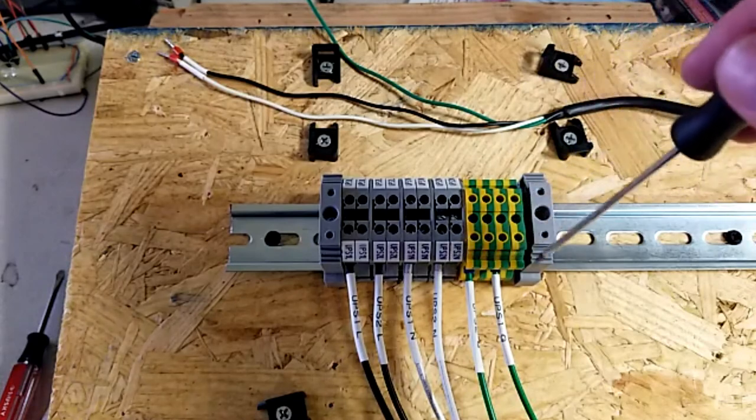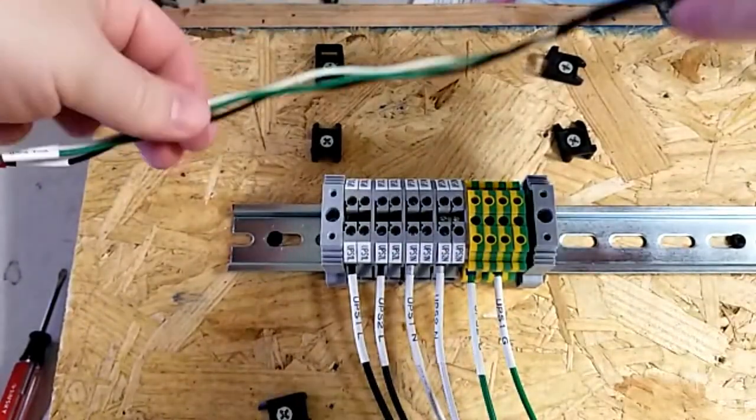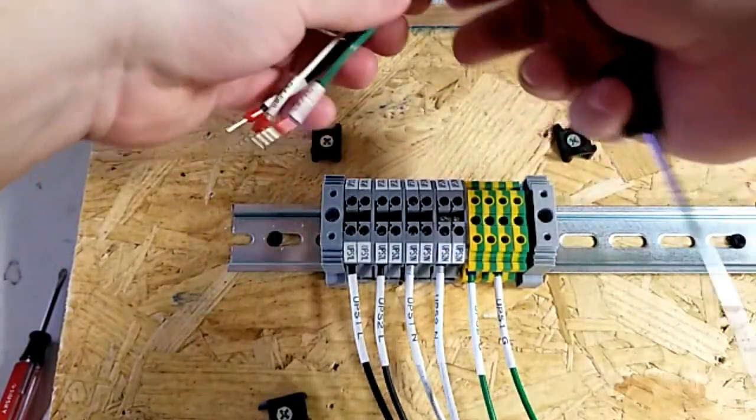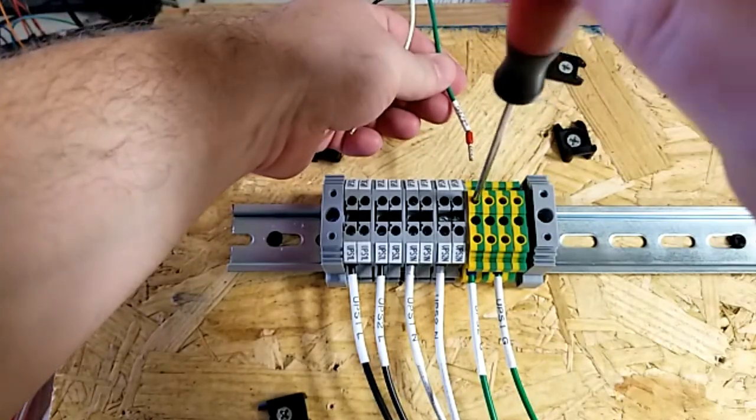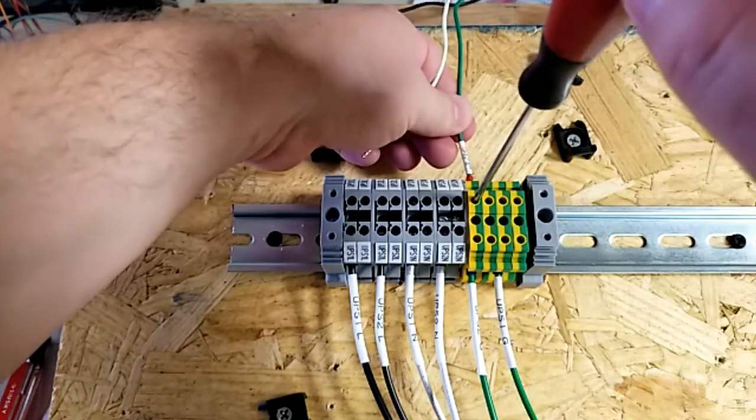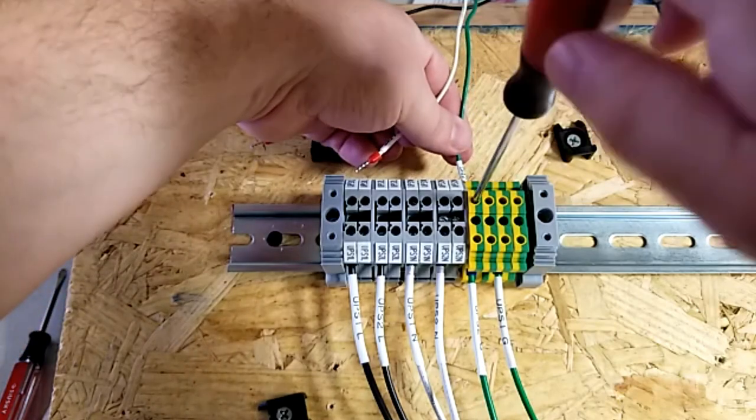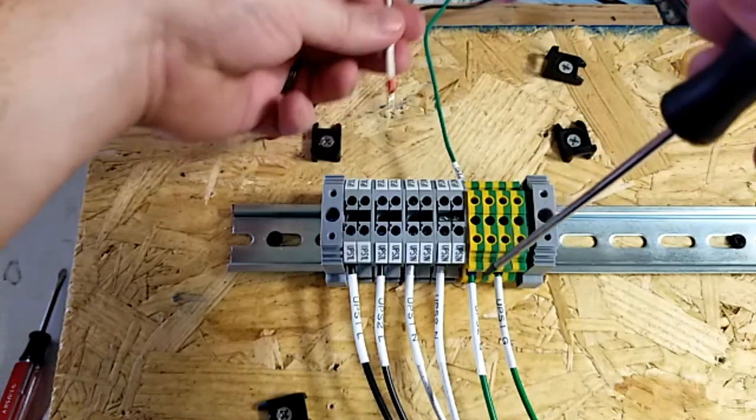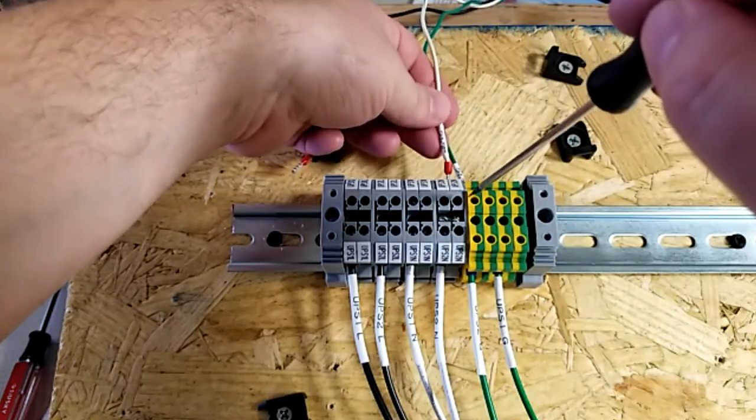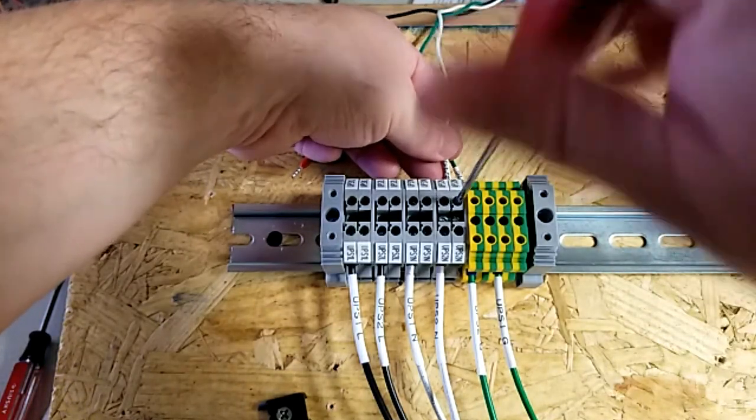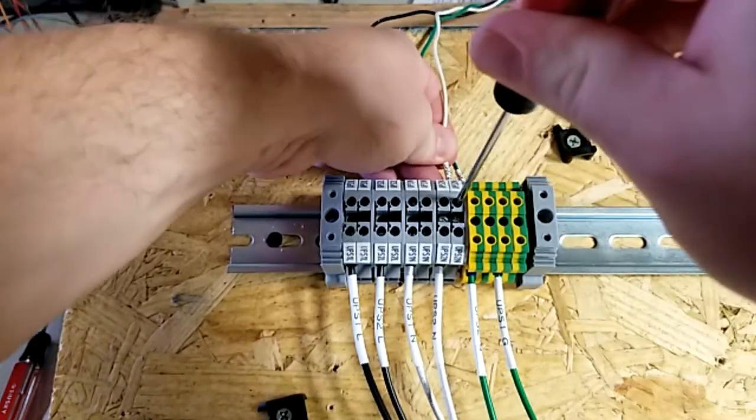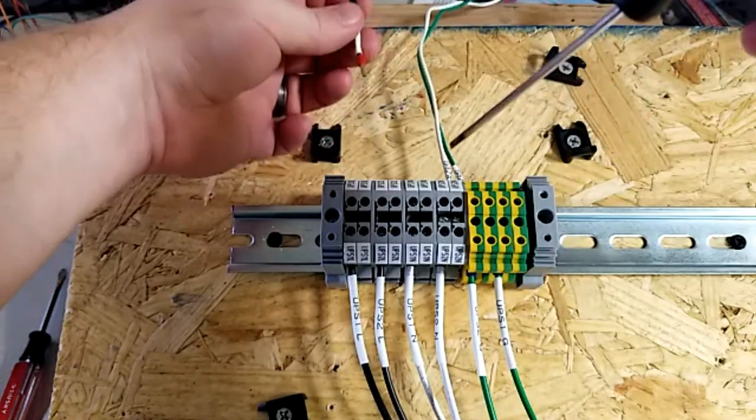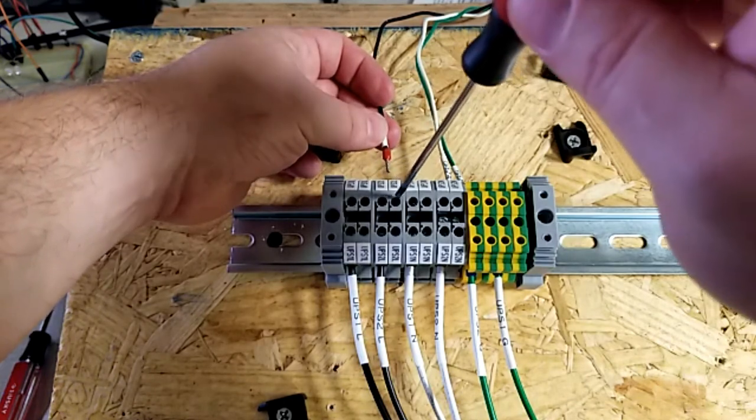Once my neutral's back in place, all my grounds are in place, I can then bring my new power cable for UPS4, and I'm going to wire that back in. The green wire is going to go into any of these ground terminals. So, pick a ground, loosen up the screw, make sure your wire's fully seated in there. Tighten down, give it a tug test. The white wire is going to go into either one of these two UPS2 neutral terminals here. Again, loosen if needed. Make sure it's fully seated. And then tighten down snug. And then the black wire needs to go into one of the UPS2-L terminals.